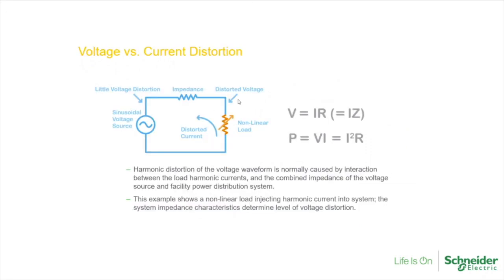And now some differences between voltage and current distortion. Harmonic distortion of the voltage waveform is normally caused by interaction between the load harmonic currents and the combined impedance of the voltage source and the facility power distribution system. This example specifically is showing a nonlinear load injecting harmonic current into the system, and the system impedance characteristics determine the level of voltage distortion.